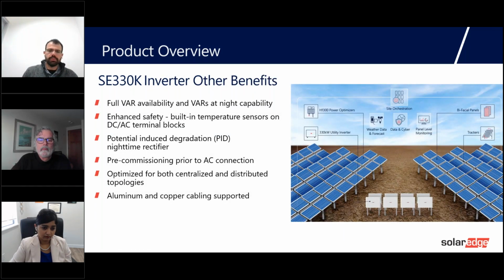A few more points on the product. This is way ahead of its time at this point, but this inverter, if needed, has full VAR availability. In other words, it can produce the whole 330 kVAR. And if needed, this inverter can also do VARs at night. So far, there's no requirement, but we see that coming, so we want to have that ready.